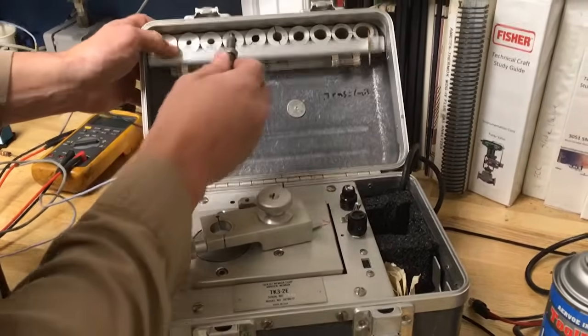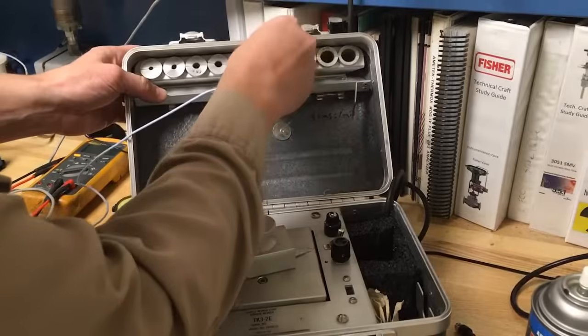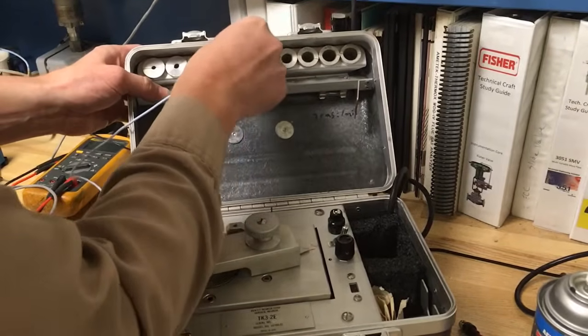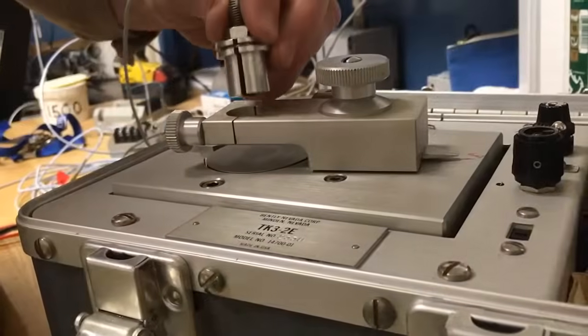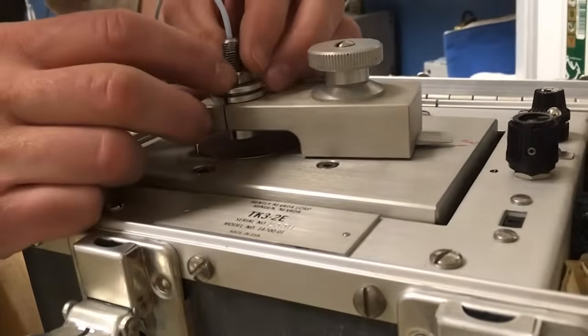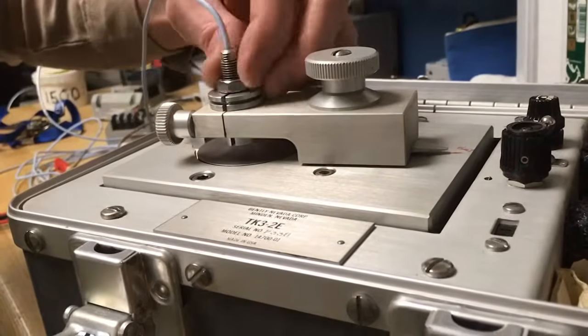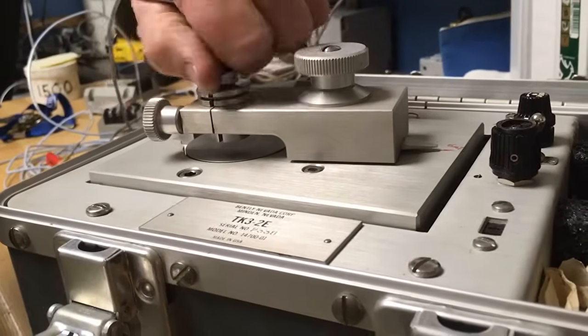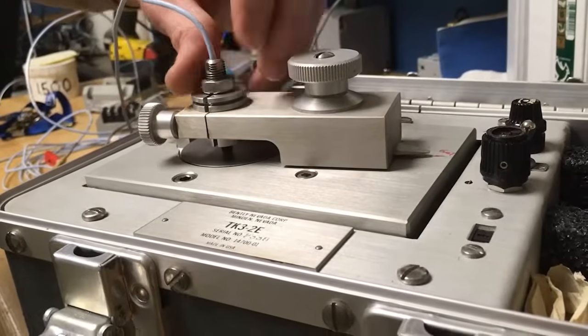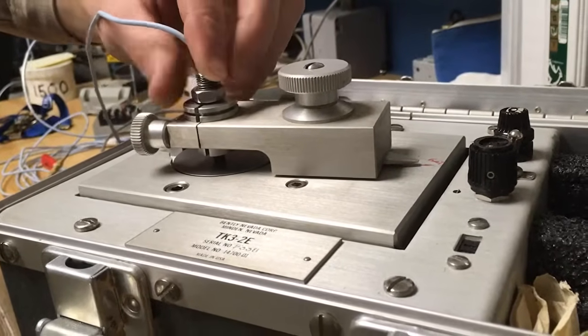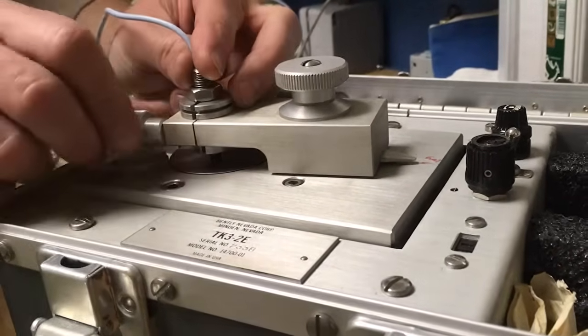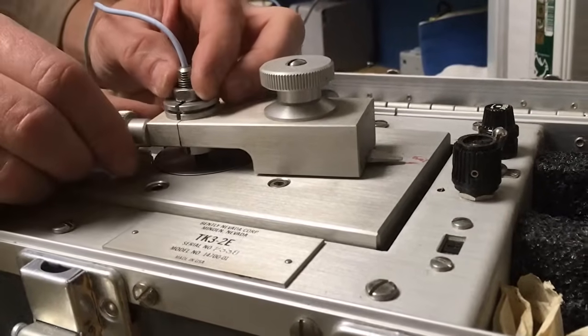Select a bushing that fits the proximity probe to be tested. Mount the probe in the swing arm in the same manner as you did the dial indicator. Let the probe rest on the surface of the disc. It may be necessary to loosen the locking nut to provide the probe with adequate insertion length.